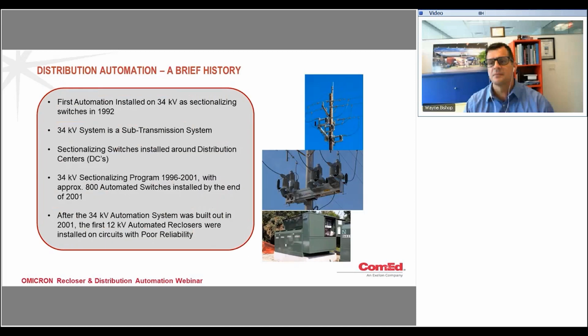So let me start off by giving you a brief history of the DA program for ComEd. Our first automation was installed on our 34 kV sub-transmission system as sectionalizing switches in 1992. These switches were installed around distribution centers, which typically feed our 12 kV system. So our 34 kV program ran from 1996 to 2001, in which we installed about 800 automated switches by the end. And after our 34 kV system was built out, the first 12 kV automated reclosers were installed on circuits with poor reliability, which leads me into the next slide.